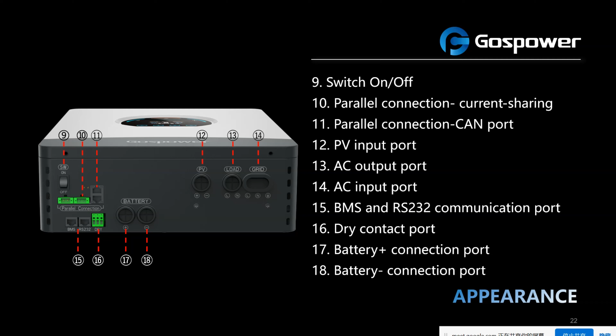The inverter has 1 PV input port, 1 AC load output, and 1 grid AC input. It is standard with a BMS communication port and an RS232 port. The BMS communication port is used for connecting with the lithium battery, and the RS232 is used for connecting with our laptop to do any upgrades for the inverter. Beside them, there is a dry contact for the generator, which sends a signal to control the generator on or off. Beside that, you can find the battery positive and negative ports.